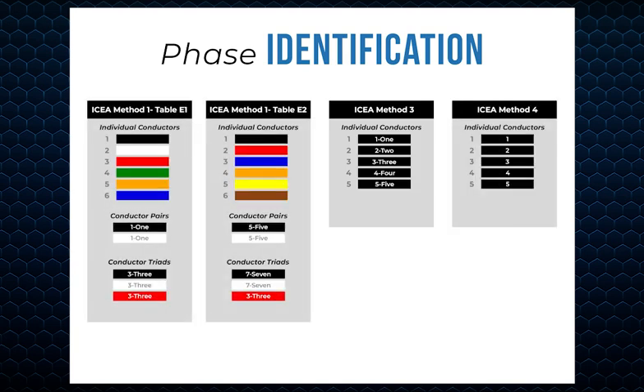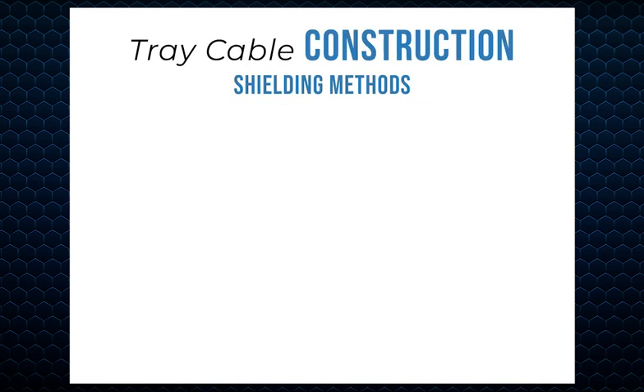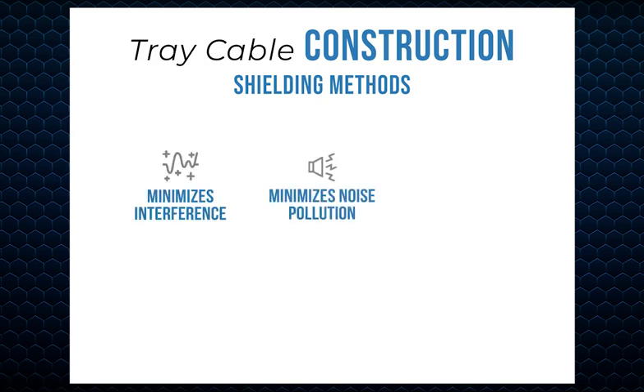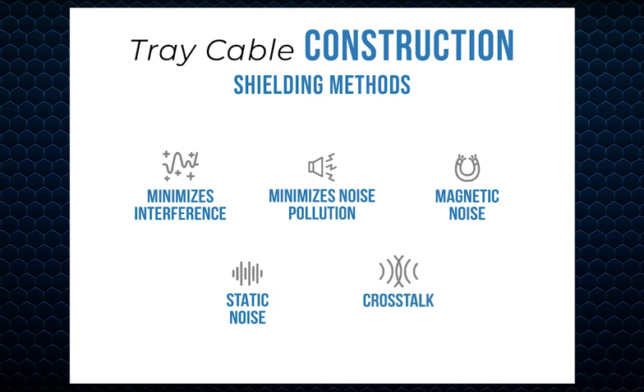Remember, you should always verify the end user's specific color code methods. Certain applications may require the tray cable core to be shielded. When required, shielding minimizes interference from outside disturbances and keeps inside electrical noise from polluting the environment. Types of electrical interference include magnetic noise, static noise, and crosstalk.